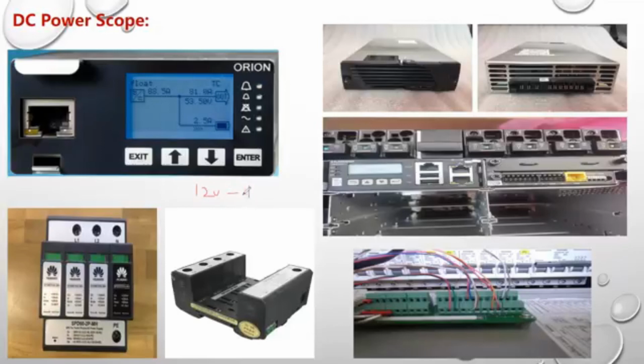I need 4 of them to give me the 48 volt DC. And 2 volt batteries, I need 24 to give me the 48 volt DC. Now, if all of your talk is about 48 volt DC, then why is the volt that appears on the rectifier like 53.5 volts or 54 or 54.5? How did this come? And I'm supposed to be actually 48.